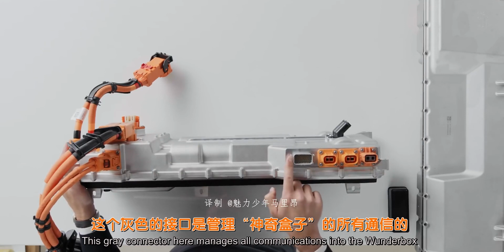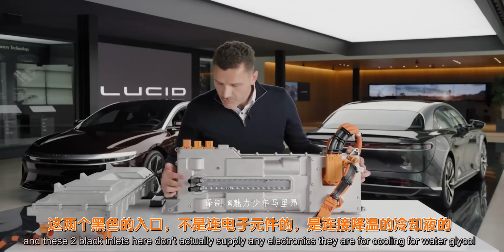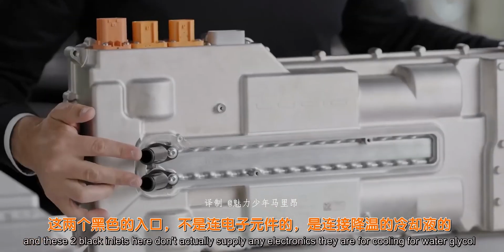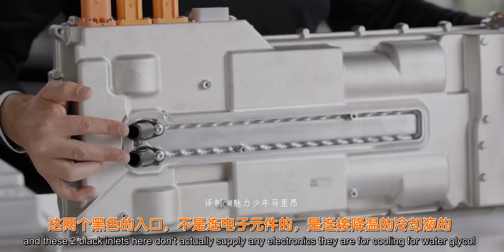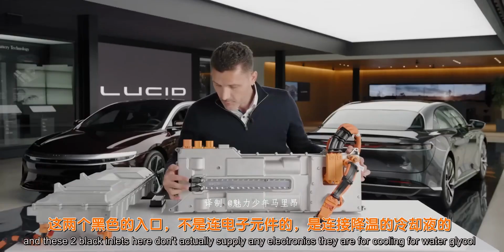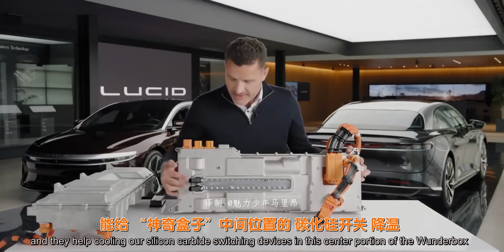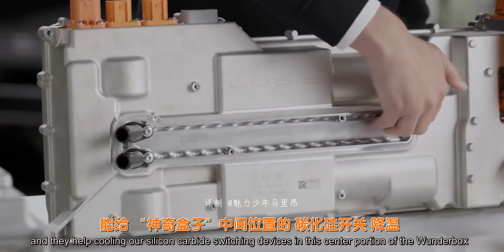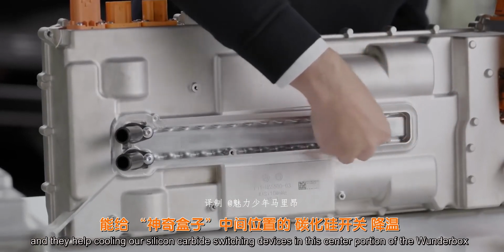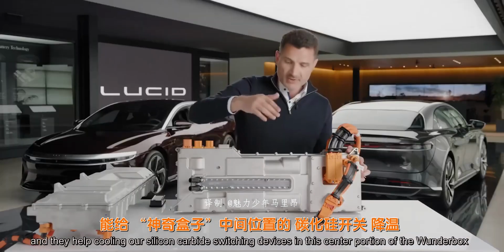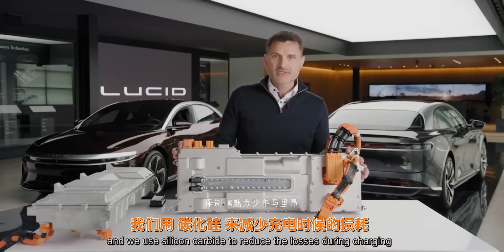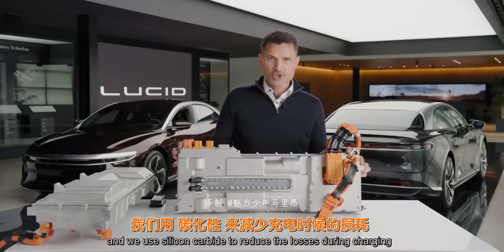This gray connector manages all communications into the Wunderbox. These two black inlets don't actually supply any electronics—they're for cooling, for water glycol, and help cool our silicon carbide switching devices in the center portion of the Wunderbox. We use silicon carbide to reduce the losses during charging.